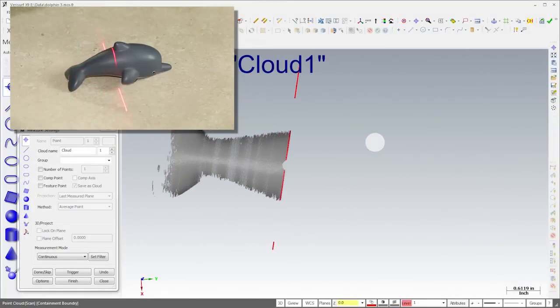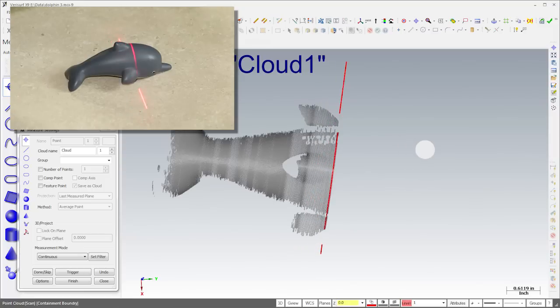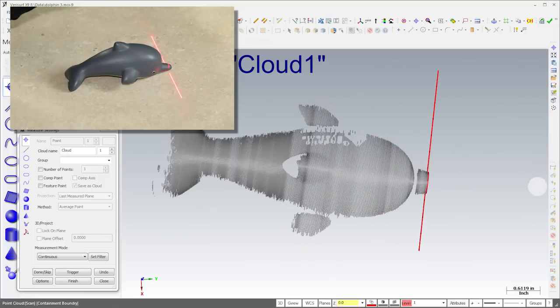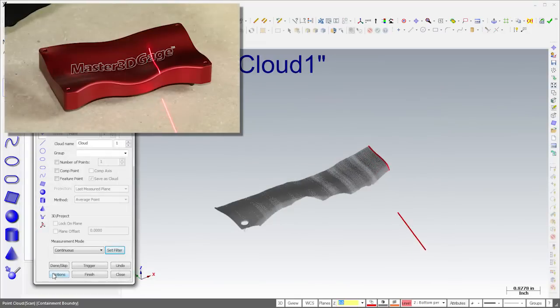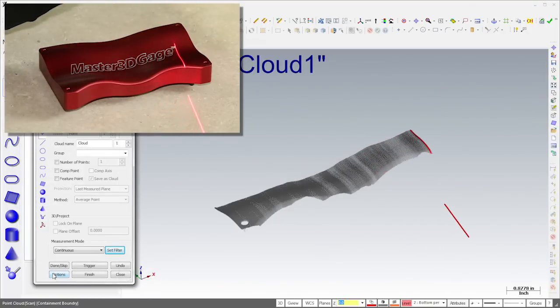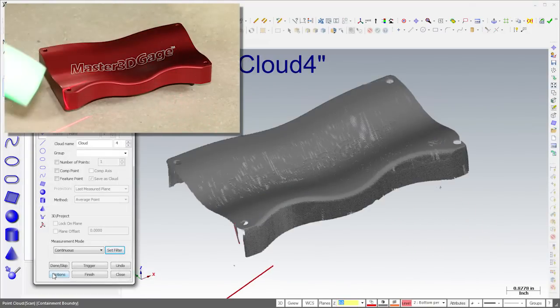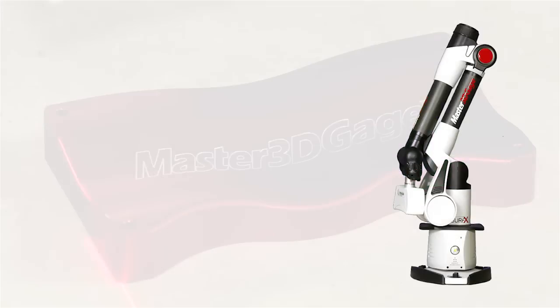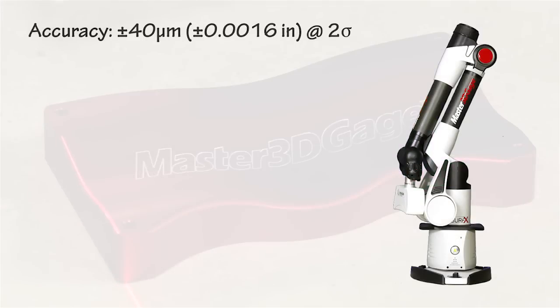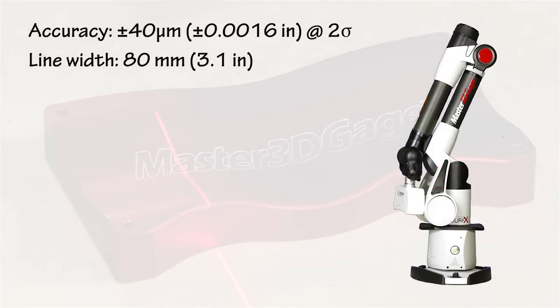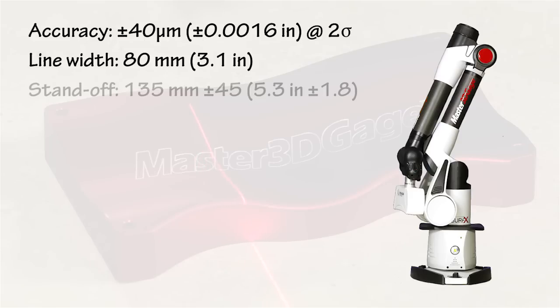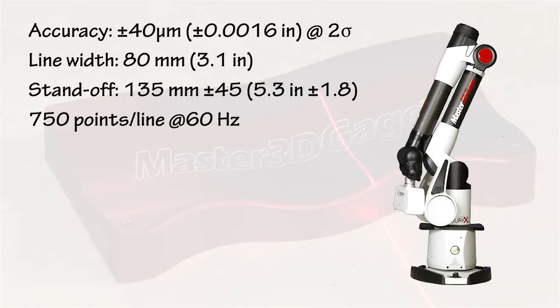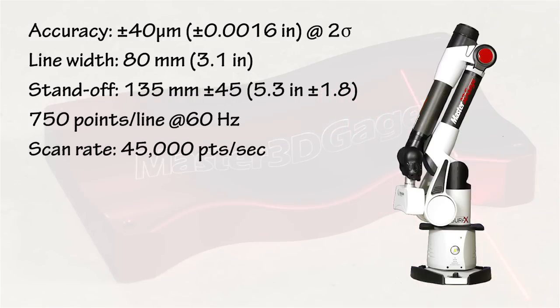The Master 3D gauge scanner enables high-speed, non-contact 3D point capture at a great price-performance ratio for analysis and reverse engineering. The scanner accuracy is ±40 microns at 2 sigma. Line width at midfield is 80 mm, and a long standoff distance enables scanning in hard-to-reach cavities. The scanner measures 750 points per line at 60 Hz, for an effective scan rate of 45,000 points per second.